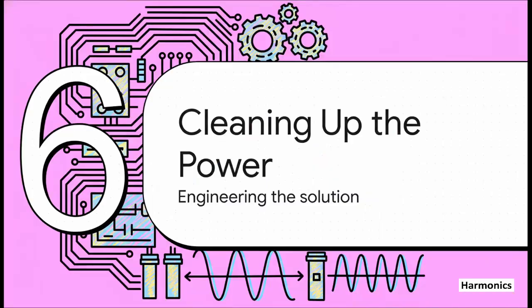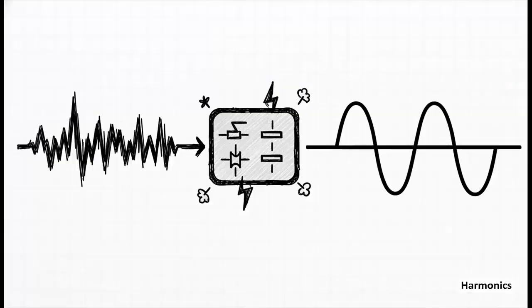Now, the good news here is that this isn't some unsolvable mystery. Not at all. Engineers have been working on this problem for a long time, and there are absolutely ways to clean up our power. The main solution is something called a harmonic filter. I want you to think of it like a pair of noise-canceling headphones, but for your electrical system. It's specifically designed to either block or absorb all those unwanted harmonic frequencies, which lets only the pure, fundamental wave pass through. The result is a much cleaner and much more stable power supply for everything.